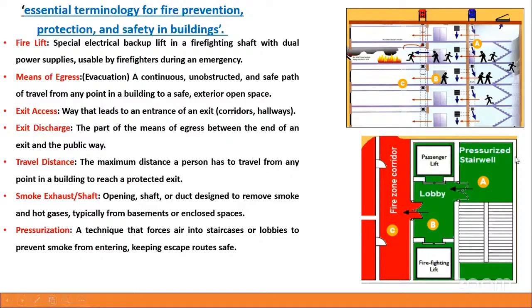We can see a green portion in a staircase or lobby area, and a red portion in the fire hazard zone. What is this green portion? It is a pre-pressurized, vacuum-evacuated space, where we have to take care that a person evacuating from this lobby, either from the lift or staircase, is not affected by fire spreading inside. For that, pre-pressurization is done.